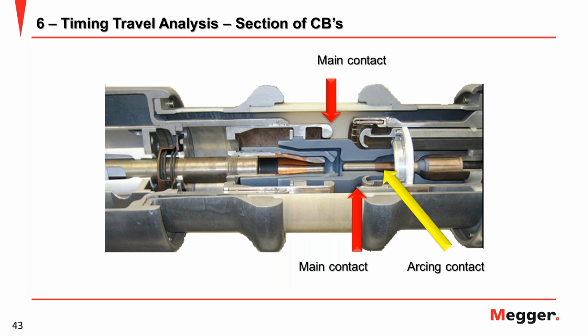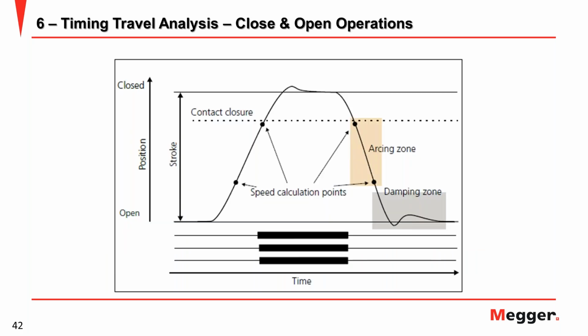And also you can calculate the speed, how fast the breaker operates. And you can also find the arcing zone condition, and the damping zone if the breaker has a damping part. But the important things for medium voltage, I think, are the stroke value and speed. If you can measure them, then you will get more information about the mechanical issue of the breaker.